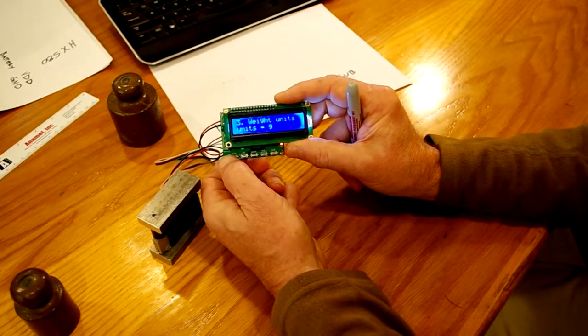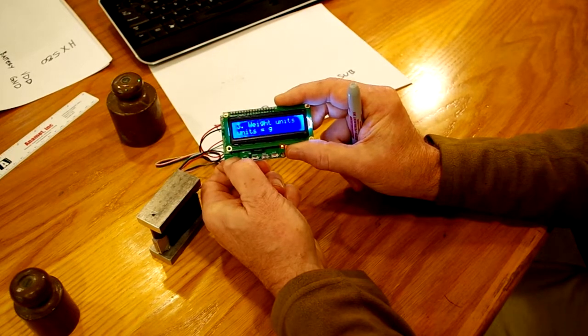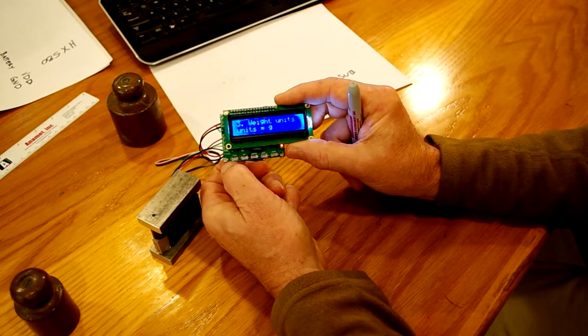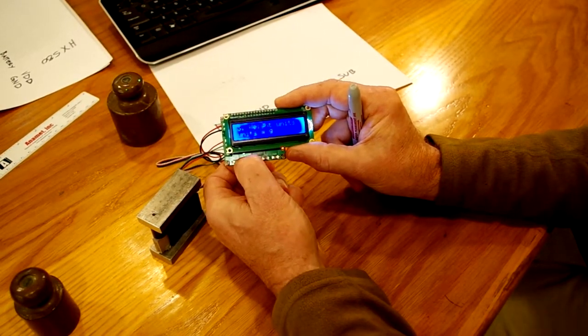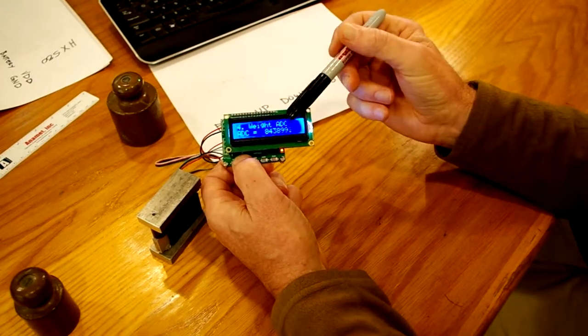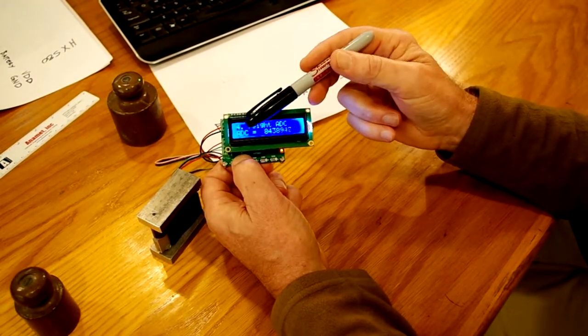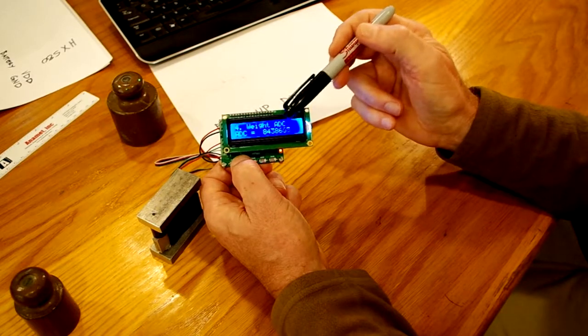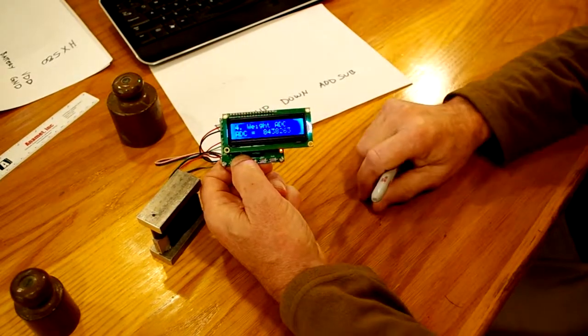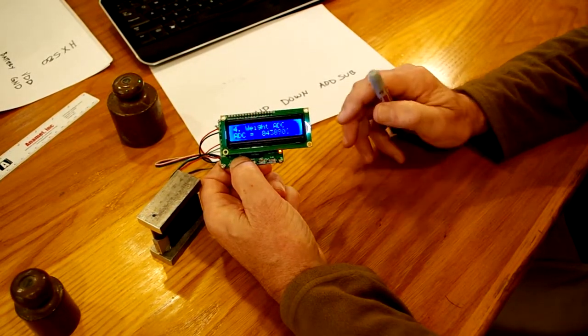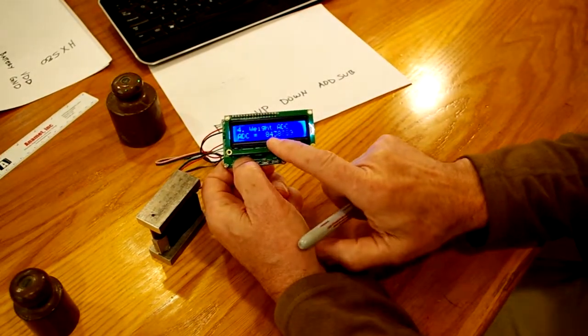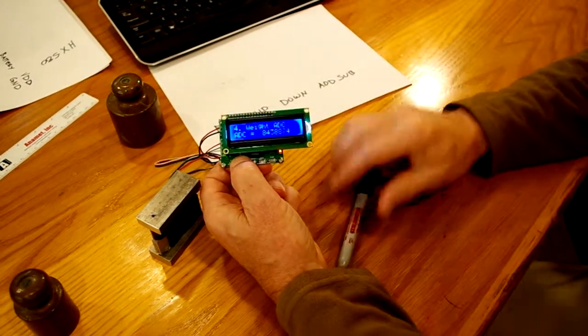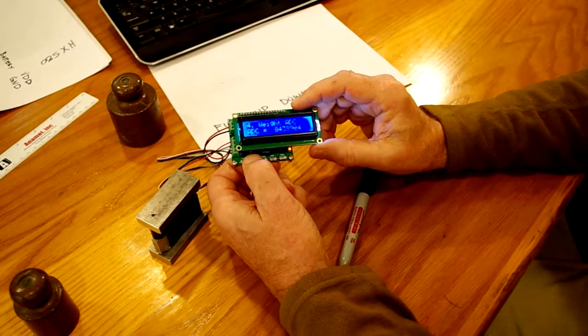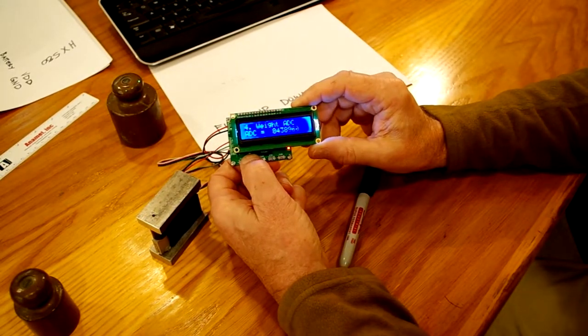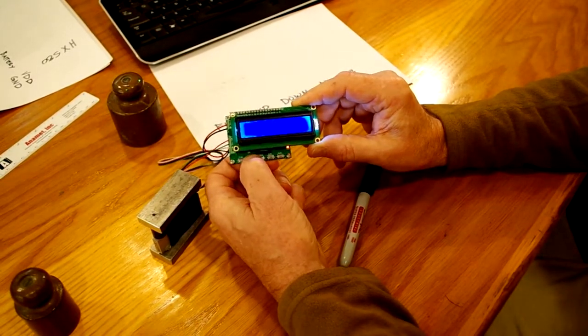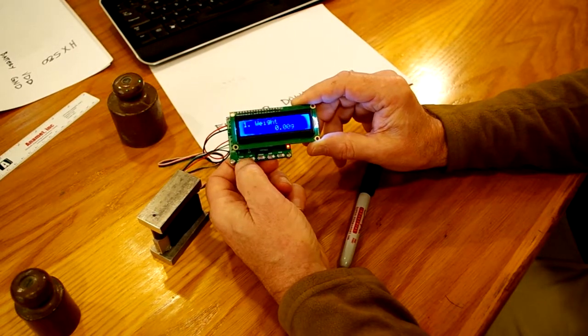And if we hit the function key again, we go to number 4. Not the function key, hit the up key. We go to number 4. I think this is the analog to digital converter reading. It's a 24-bit converter, so this is just the number that represents the voltage that's coming into the unit at this point. And if we hit up again, we're back to the displayed weight.